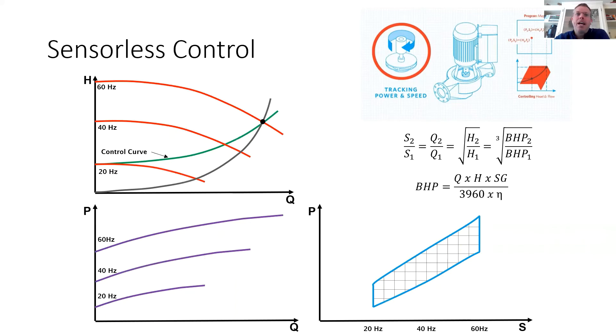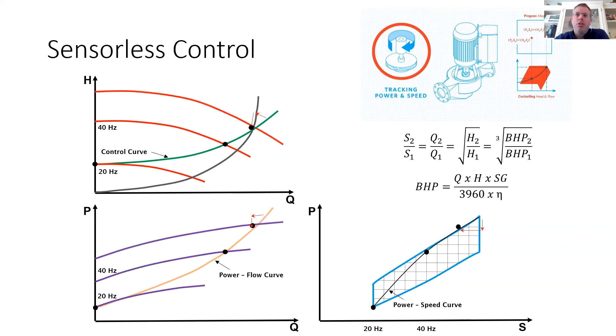So that control curve also generates a corresponding power and speed curve. And so as valves start to close out of the system, your flow is going to drop and your head is going to increase, but it's going to be in a square root relationship. So the resulting power consumption at that given speed is actually going to drop. So that's going to take you off the power-speed control curve, and in order to get back onto the control curve, the pump controller will slow down the speed of the pump until the appropriate power consumption is reached via their map.